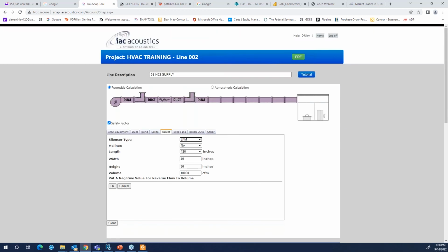That's important. When you're dealing with 1 silencer or 2 silencers or 3 silencers, especially 2 and 3 in sequence in a run, you really want to work with the same type of baffle arrangement to make sure that as air flows in and out of the silencer, it flows proportionally and directionally. And again, that's important. If you are changing the direction of airflow from one silencer to another within a system, it could cause self noise within the system.